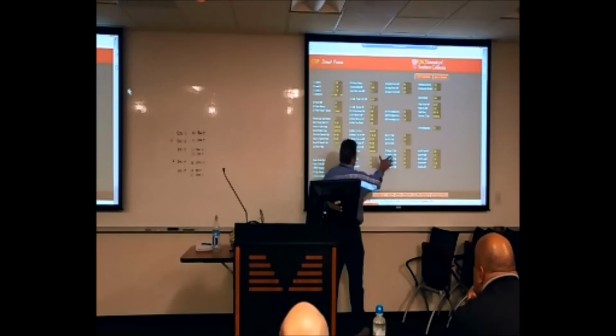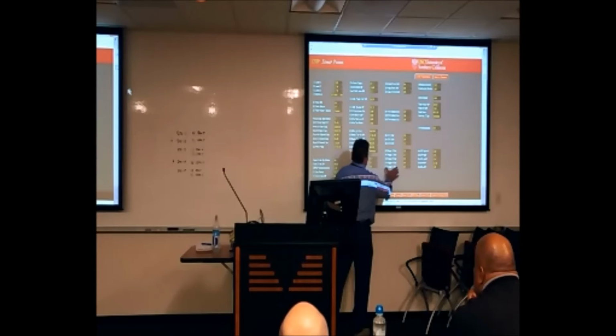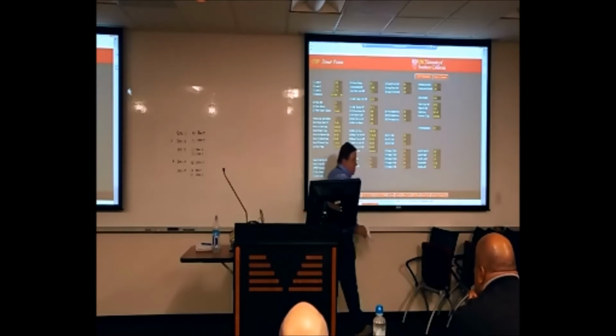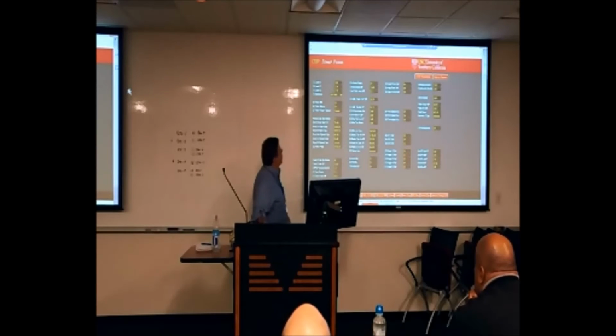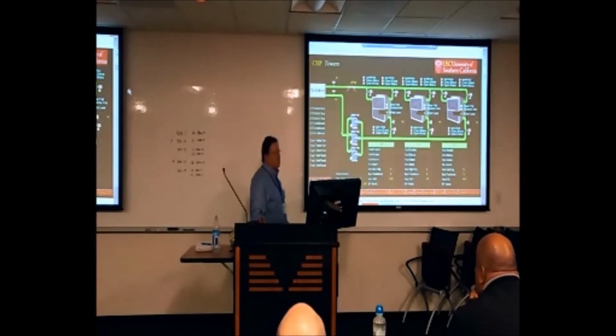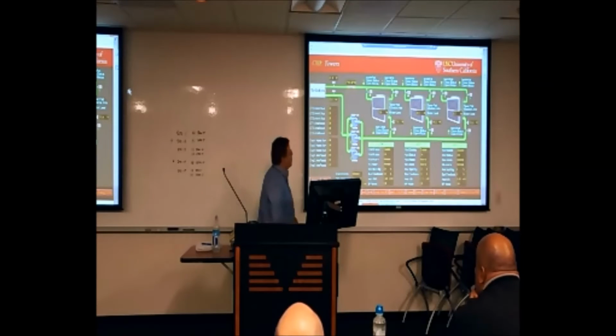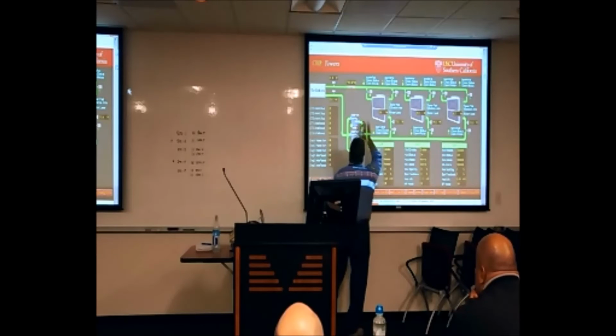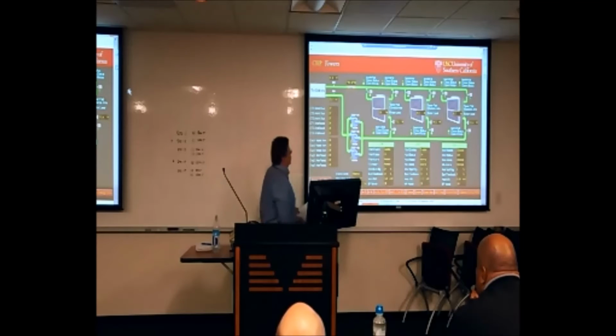And for example, here's our stage calls over here. So right now it does see the one 1,500-ton chiller online, so we're asking for stage number 2. And going back to our tower graphic, we're running the 2 cells with the 1 pump, which is the stage 2 criteria. I'm kind of doing the overview right now.